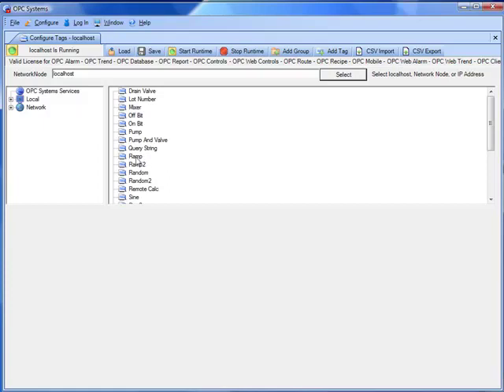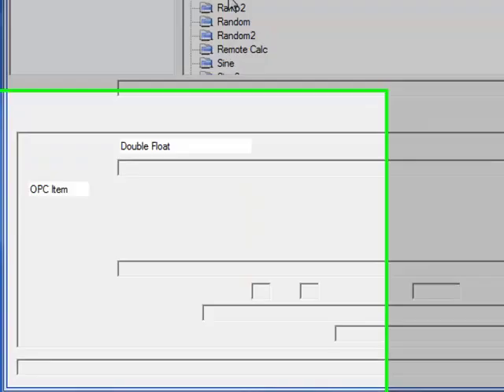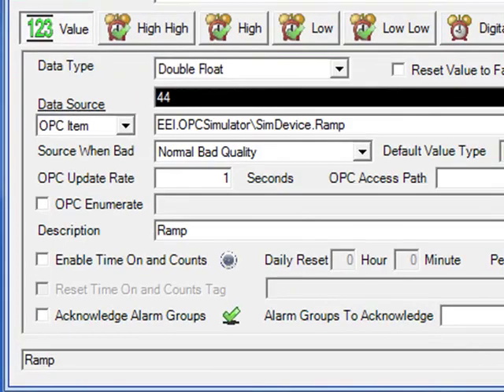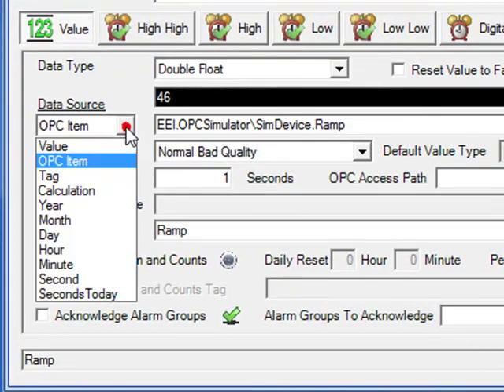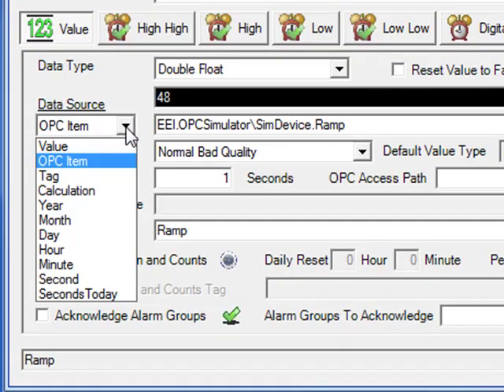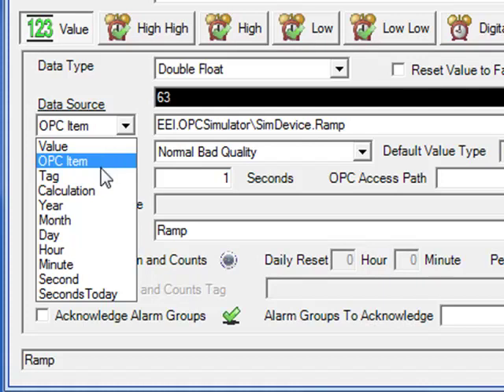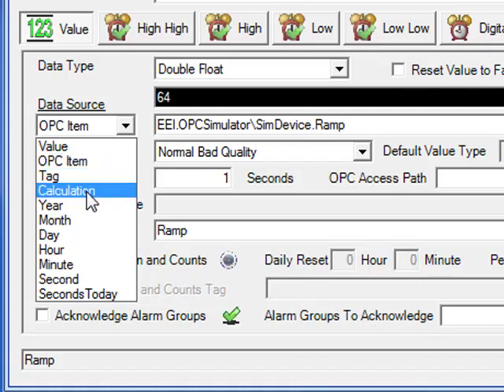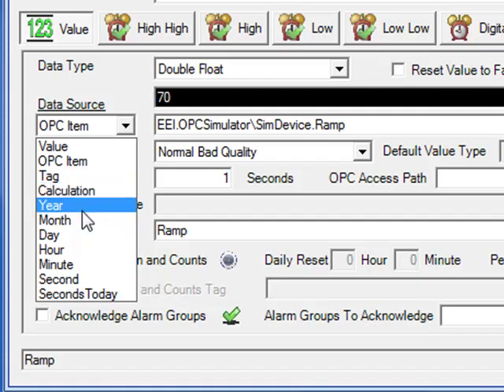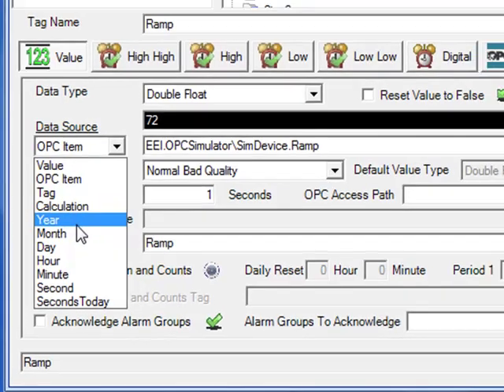An opcsystems.net tag can be defined with a data source of a fixed value, which would then come from a Visual Studio application, an OPC item coming from an OPC server. It could also be coming from an OPC client with the product feature opcclient.net. It can be coming from a remote tag or even a calculation, which would be a composite of multiple values together in some kind of math equation. And also you can have as a data source the CPU clock.